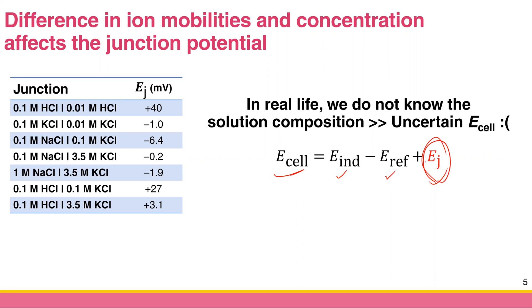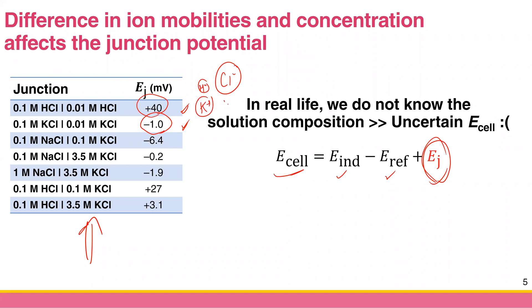There are ways to predict junction potential. Consider the first two entries in the table: hydrochloric acid has a junction potential of +40 millivolts, while potassium chloride has only about 1 millivolt. This is because proton is much smaller than chloride, giving a large potential difference. Potassium and chloride have relatively similar sizes, so the potential difference is much smaller — that is why potassium chloride has much lower junction potential.